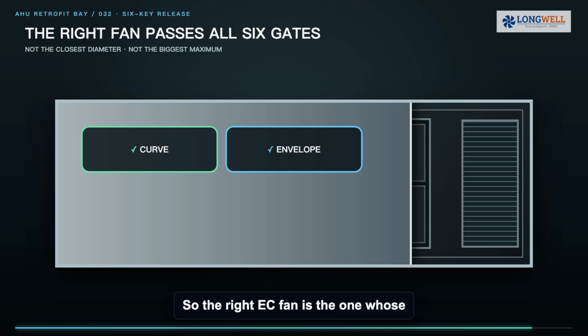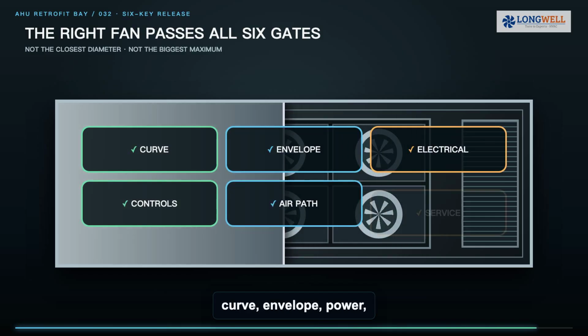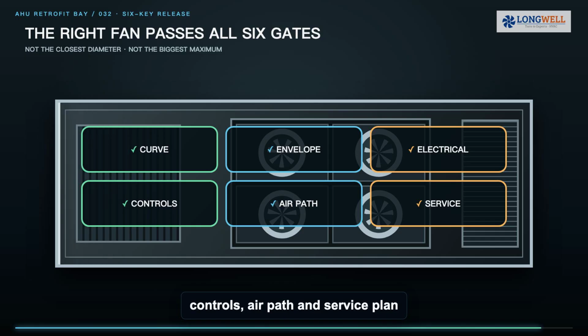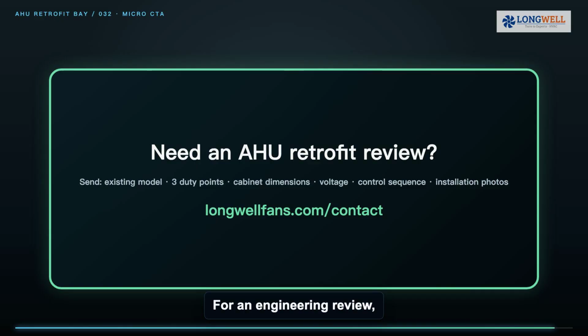So the right EC fan is the one whose curve, envelope, power, controls, air path and service plan all pass together, not the one with the closest diameter or the biggest maximum airflow. For an engineering review, send the existing model, 3 duty points, cabinet dimensions, voltage, control sequence and installation photos.